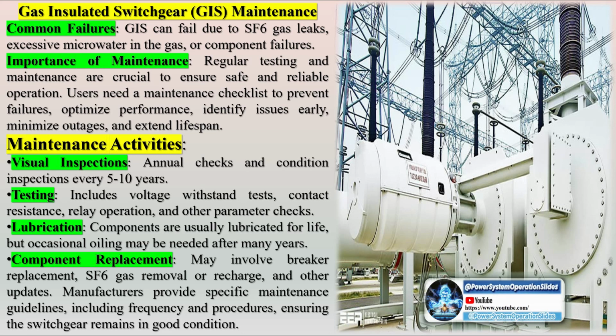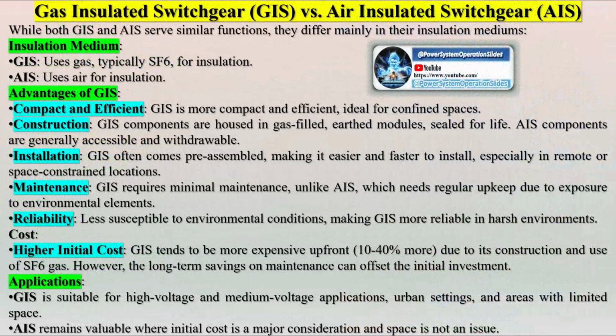By enclosing components within modules, GIS prevents arc-causing incidents like vermin entry or conductive dust accumulation. This reduces arc flashes and increases overall safety. Additionally, SF6 is an excellent arc-quenching medium. GIS comes pre-assembled, making the installation process straightforward and quick. This leads to easier installations and shorter installation times.